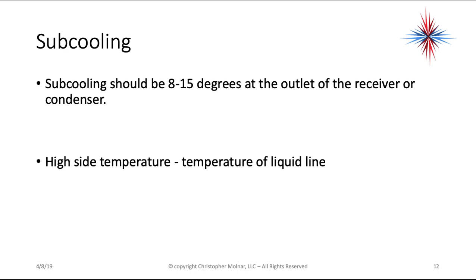Subcooling should be 8 to 15 degrees at the outlet of the receiver or condenser. The higher the efficiency equipment, this number is going to change a little bit. Subcooling is your high side temperature minus the temperature of the liquid line.